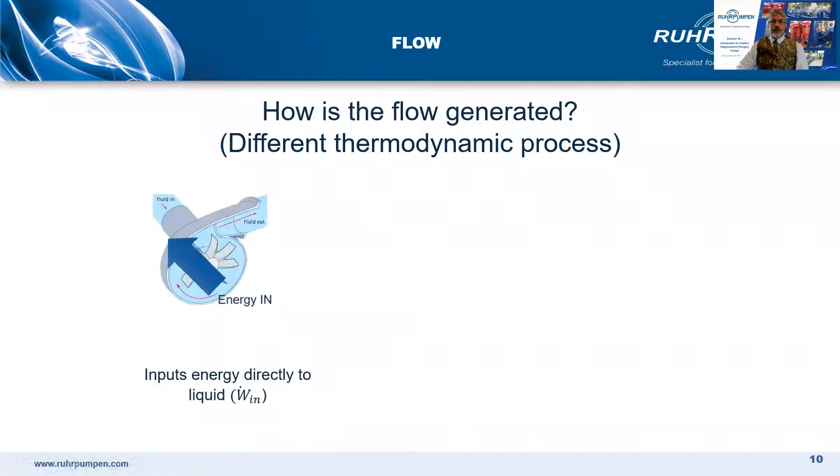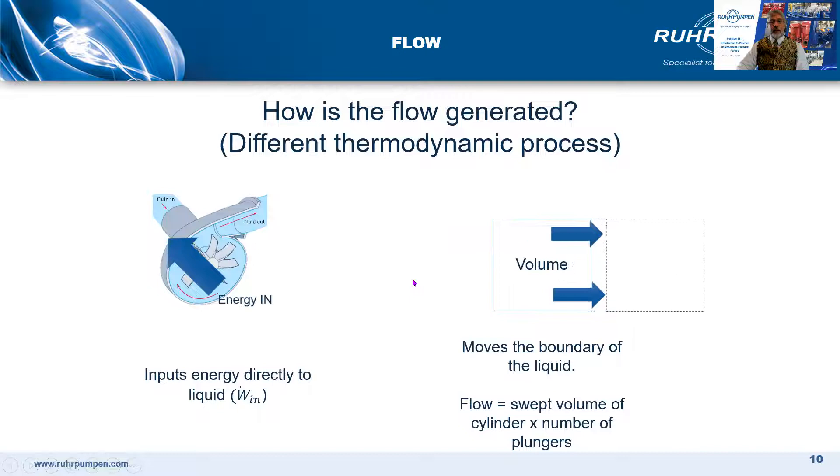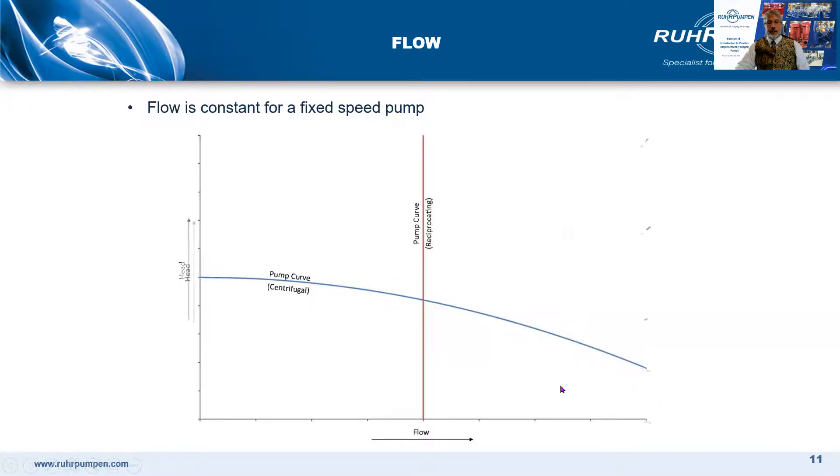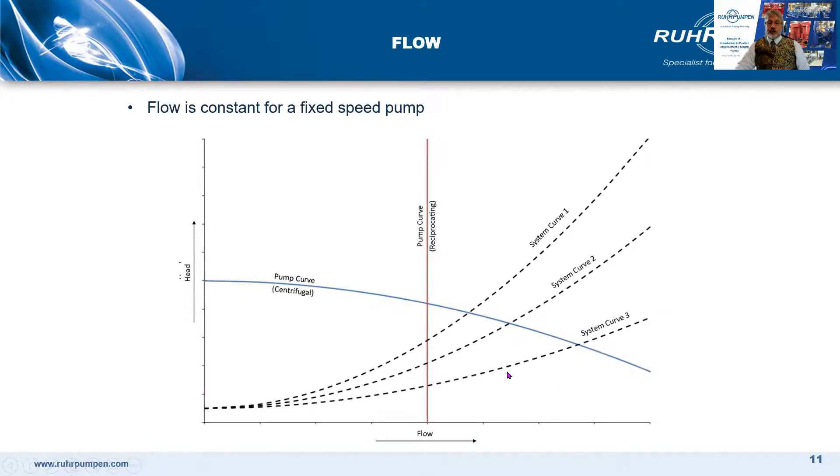With a centrifugal pump: energy in, spins the impeller, and transfers the energy to the fluid. With a reciprocating positive displacement pump, it moves the boundary of the liquid. A centrifugal pump has a pump curve, and the flow varies according to the system head. As we close the discharge valve and increase the system head, we get a family of system curves, and the flow rate is determined where the system head curve and the pump curve cross — here, here, and here.